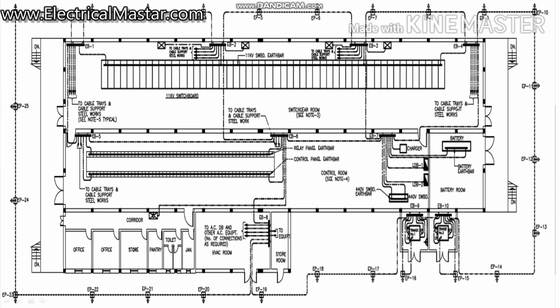So now you will understand how to read this earthing layout and what the significance is in the earthing layout, like earth pit, grid earthing, what is meant by grid earthing, the minimum distance between the grid earthing, which is 3.5 meters, and how each earth bus bar needs a minimum of 2 input supplies, and the cable size from the earth pit to the earth bus bar. I hope you know all these things. If you have any doubt you can write in the comment box. In my next video I will show how to design the earth pits, the number of earth pits required for our substation or any office premises or buildings, and also how to calculate the earth resistance value. We will discuss those things in my next video.